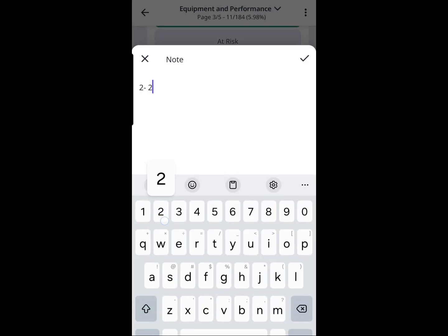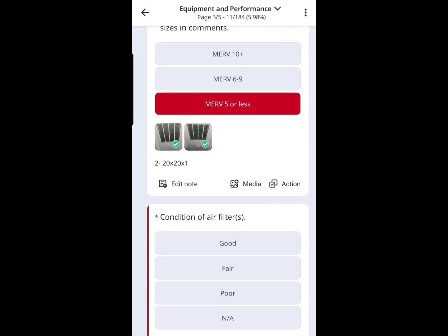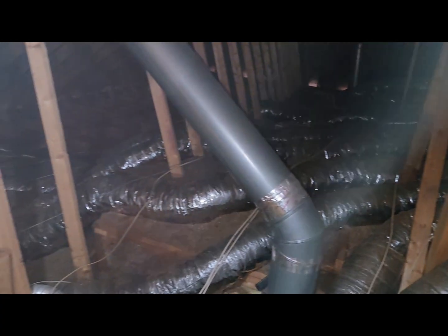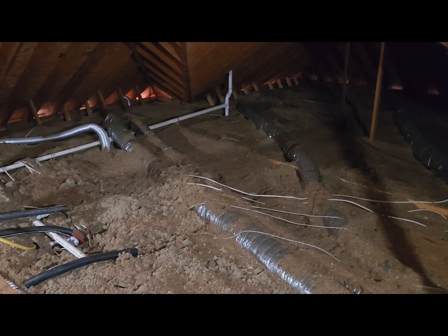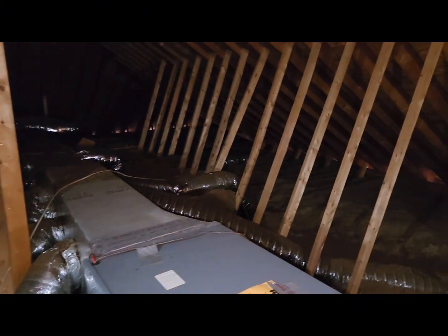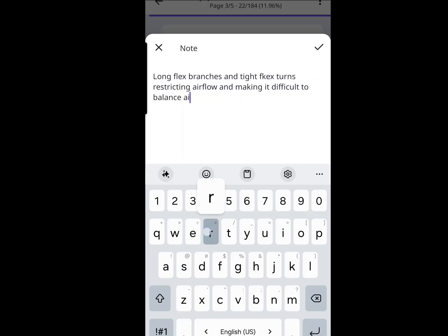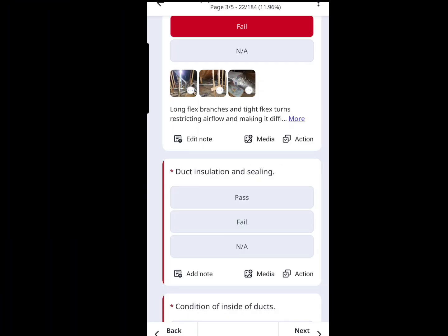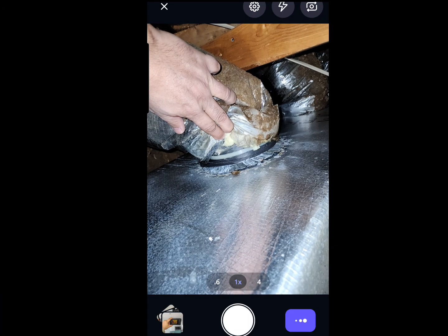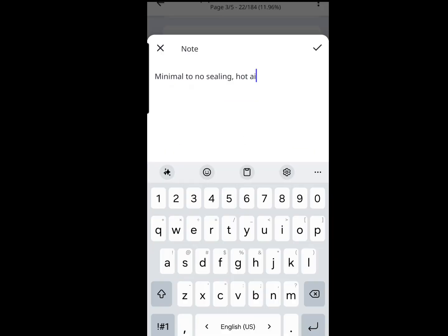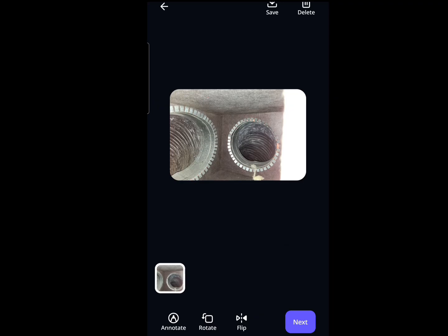We move on to the filters — we need to make sure they not only have clean filters, but we need to know whether to recommend better filtration down the road. Next, we get to the ductwork, and I think ductwork should be looked at before the equipment. We've got some really long flex runs here — that's probably going to lead to an airflow problem. There's some poor craftsmanship, so we document all that and take pictures. The ductwork gets a fail. We also look at ductwork sealing and insulation — looks like we've got some unsealed ducts. That doesn't affect the outdoor unit not coming on, but we need to document it.